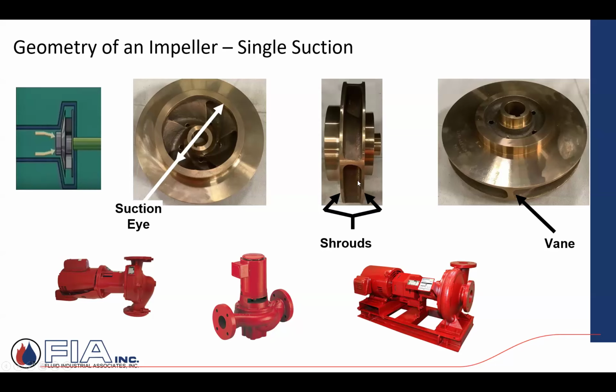When you look at it on a sideways view, I guess you could say, you could see the shroud which encloses the vanes. So that diameter, the width of that shroud, is going to change depending upon capacity, load requirements, high head, low flow, high flow, low head, whatever the conditions are. It all plays a part in the engineering and design of the pump. But the point of it all is these pumps down here at the bottom, horizontal inline, vertical inline, or end suction base mounted, those are all single suction design pumps.